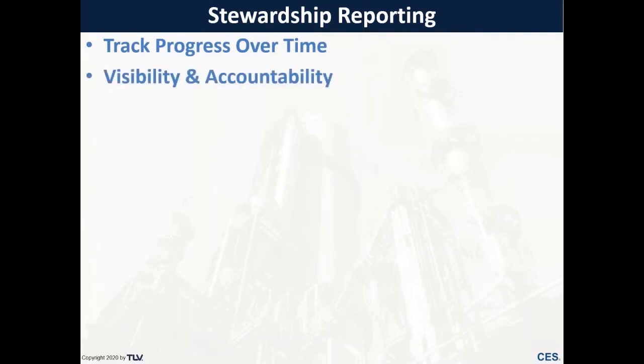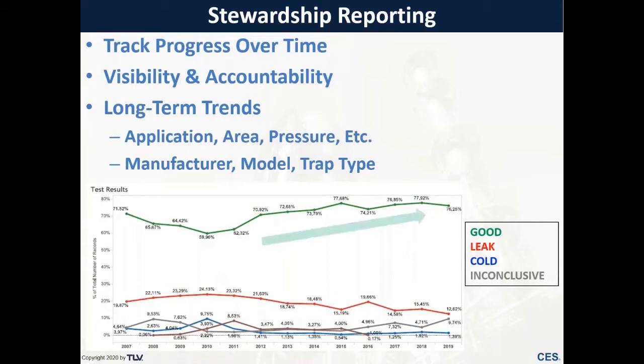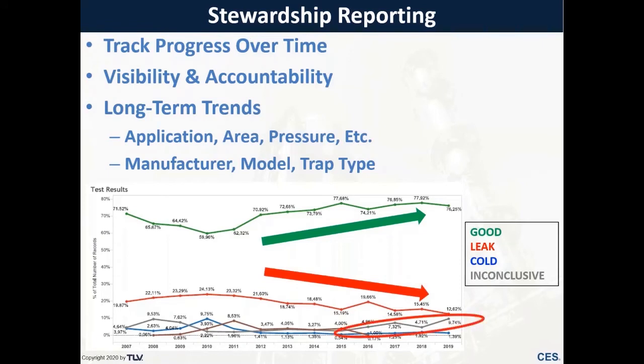A key component to CDL management is what TLV calls stewardship reporting. This reporting allows you to track progress made for your CDLs over time, provides accountability and visibility to the program, and lets you see long-term trends — which applications, areas, or pressures are performing well, or which applications have repeated failures. You can also see what manufacturers, models, or trap types are operating best for your site, and hopefully see your overall good percentage going up while failures go down.